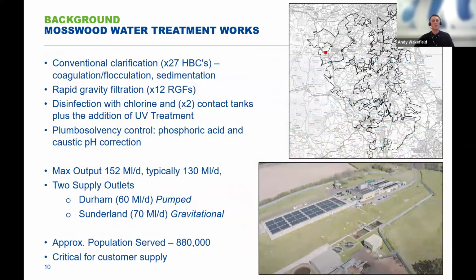So just going into Mosswood Water Treatment Works itself. The works was built around a similar time to the reservoir, so in the 1960s. And the treatment process at the time was fairly conventional, but it has had several additions over the years. The current treatment process is the addition of coagulant and flocculant to aid the clarification process and sedimentation through 27 clarifier units. Clarified water then proceeds through rapid gravity filtration, of which there are 12 rapid gravity filter units. And then disinfection is with chlorine and the addition of UV, which we'll talk on throughout the presentation.